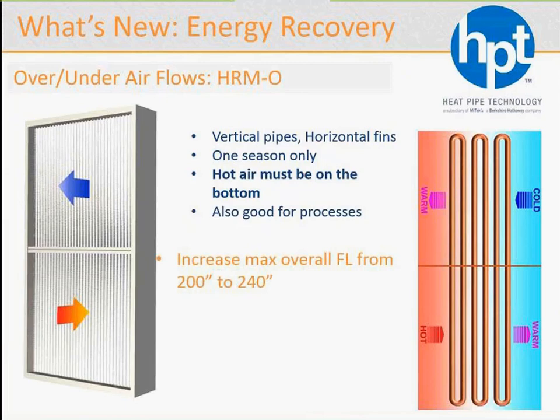Moving on. Vertical heat pipes: we've taken those circuits and basically turned them vertically, so the fins would be horizontal. So the same rules apply to the horizontal fins that you've seen in the wraparound product. This is more suited for single climates, way south where it's really only cooling recovery, and way north where it's mainly heating recovery, or in a process application whereby warm air is escaping a building, where you're trying to capture the energy that's in it. This would be very suitable.